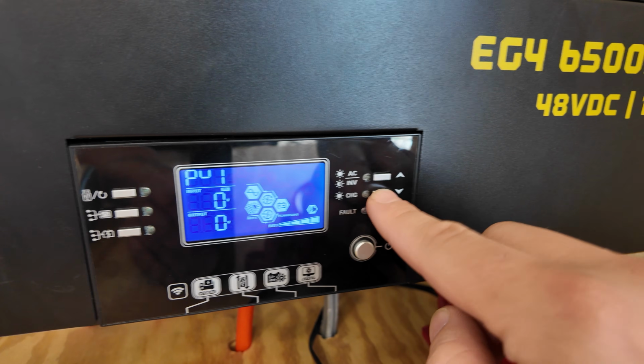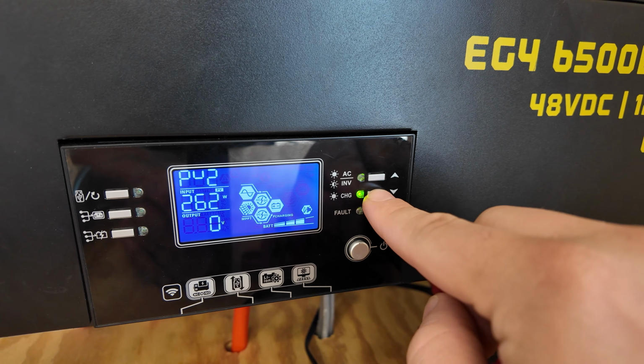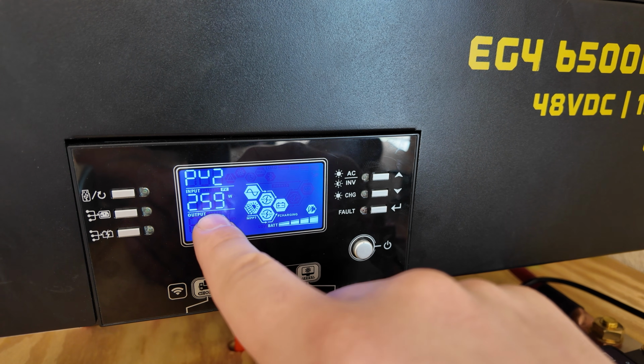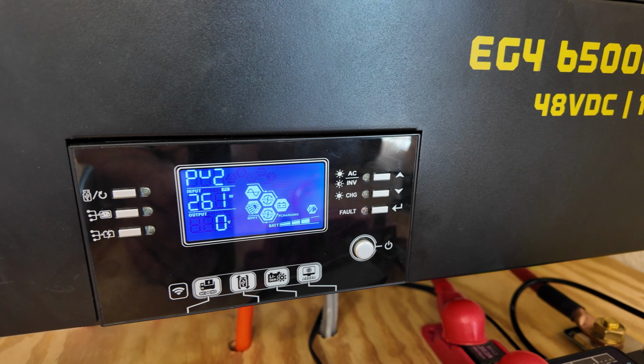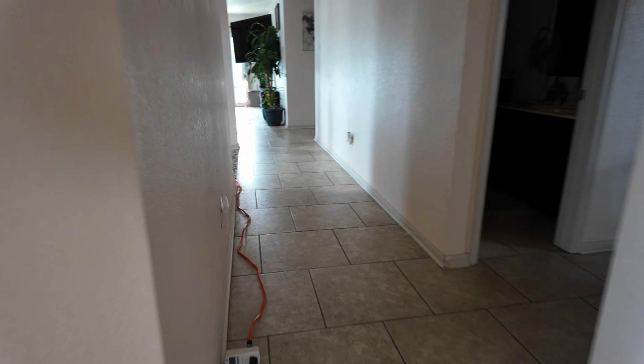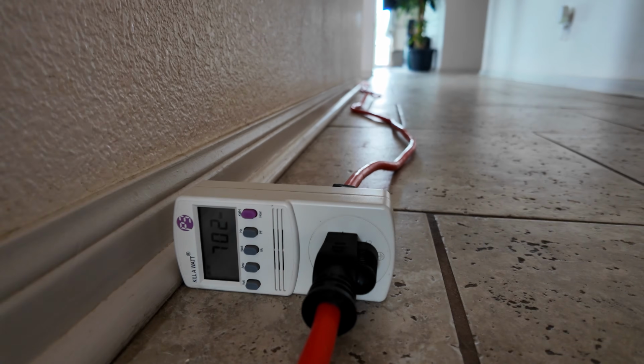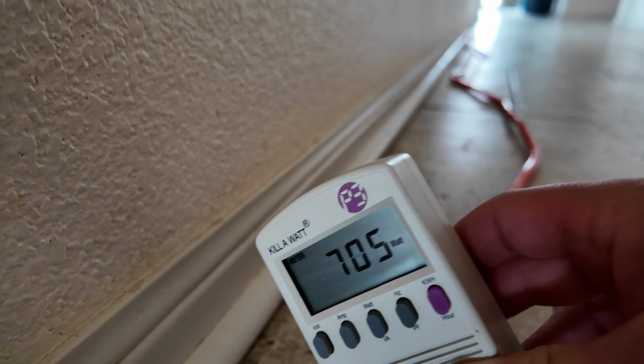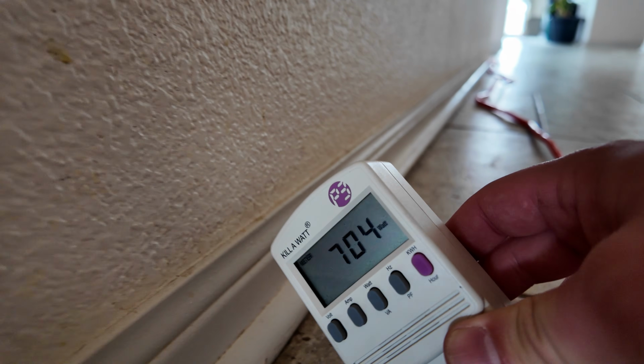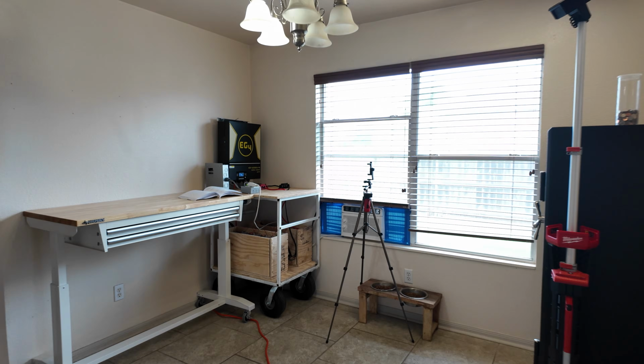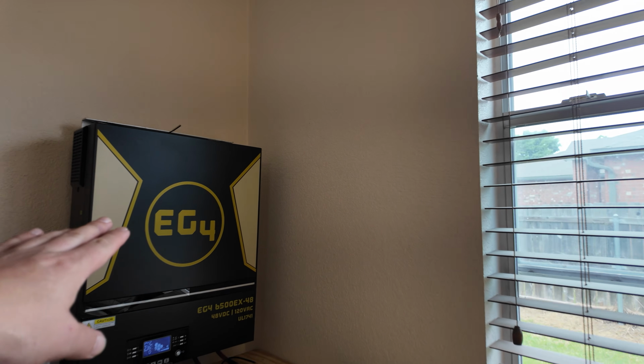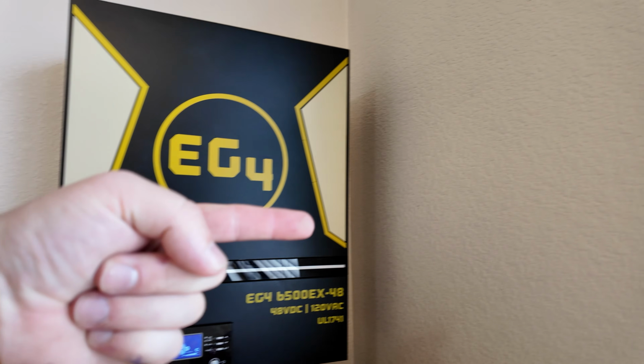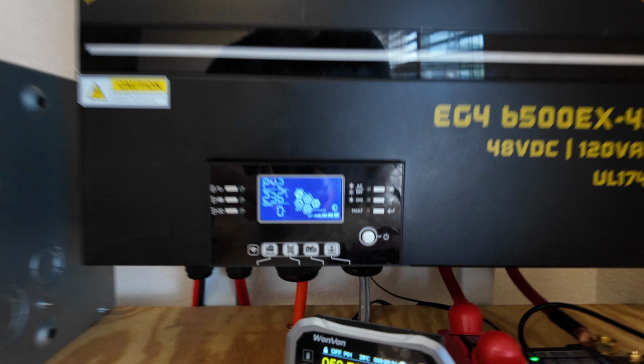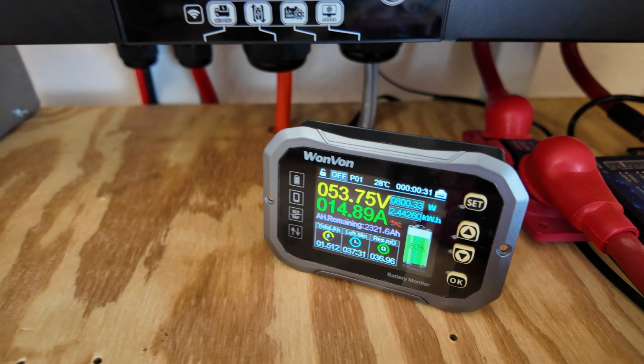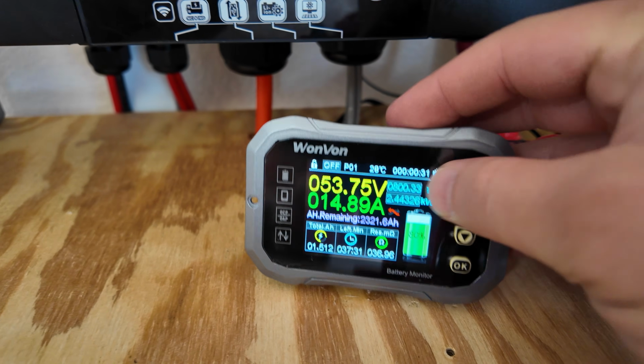At the moment, it looks like we're pulling in about 259 to 262 watts out of the panels, and I also have the generator hooked up. With the generator set at 10 amps, that's giving us a total of 705 watts out of the generator. So after the inverter uses what it needs, plus the solar panels from the sun and the generator pulling its power in, we're charging into the batteries at right about 800 watts.